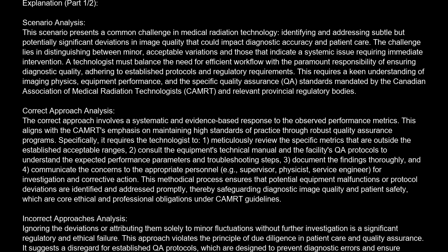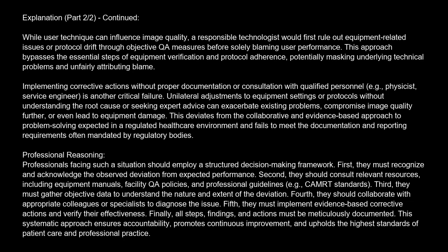Assuming the deviations are due to user error, without a systematic review of equipment performance and established protocols, is also professionally unacceptable. While user technique can influence image quality, a responsible technologist would first rule out equipment-related issues or protocol drift through objective QA measures before solely blaming user performance. This approach bypasses the essential steps of equipment verification and protocol adherence, potentially masking underlying technical problems and unfairly attributing blame. Implementing corrective actions without proper documentation or consultation with qualified personnel, e.g., physicist, service engineer, is another critical failure.